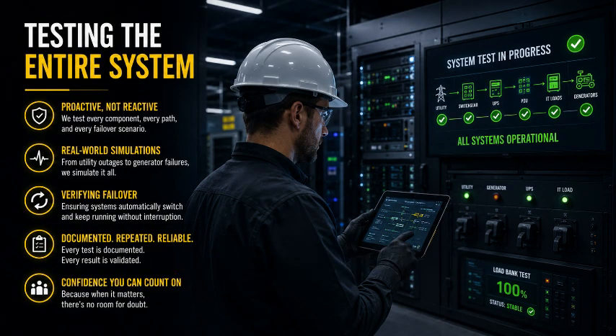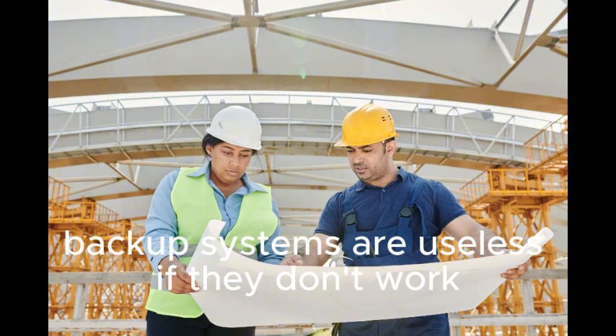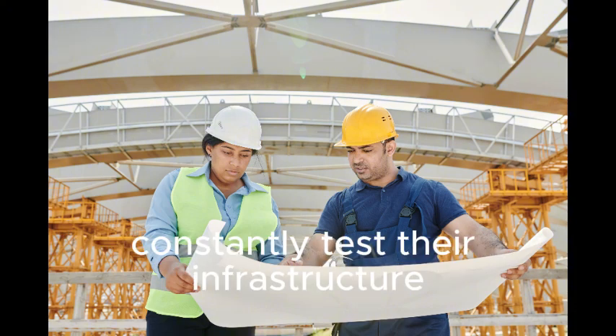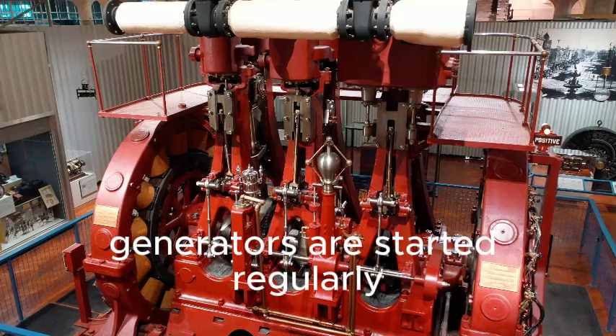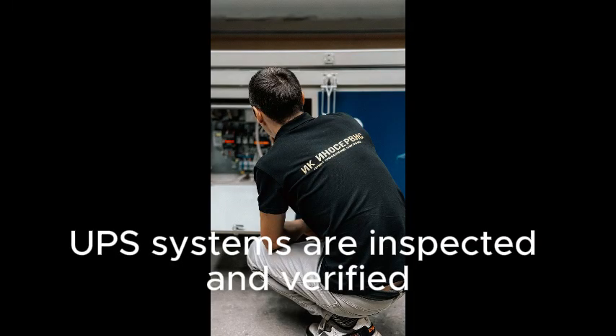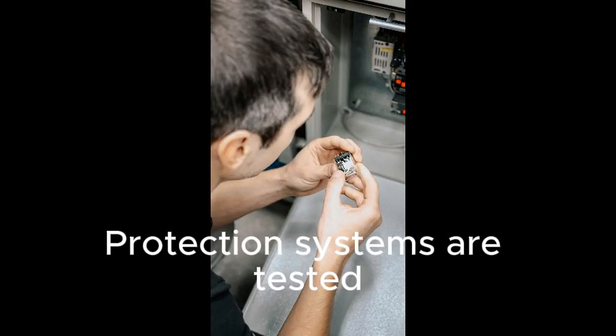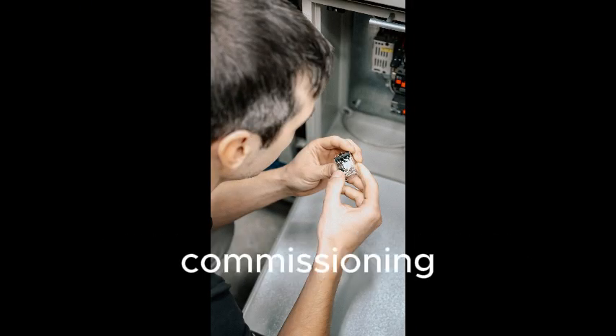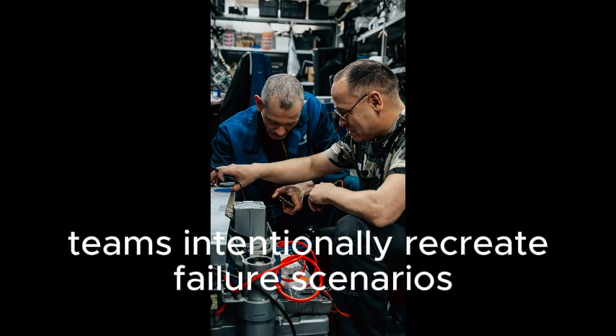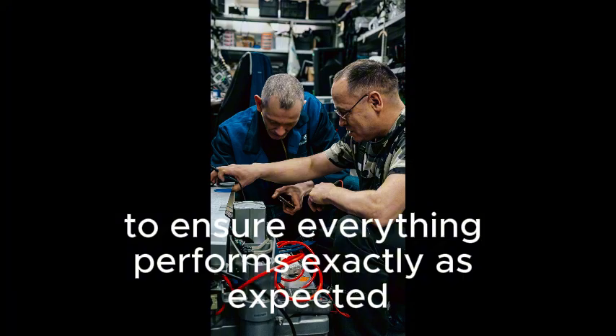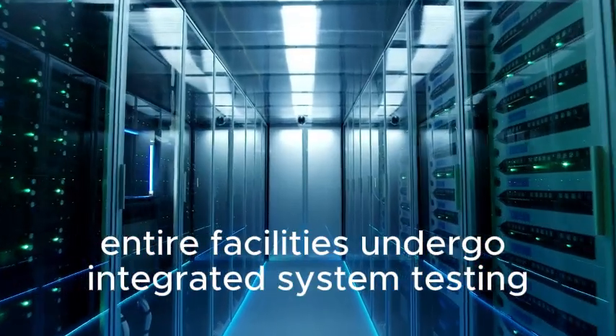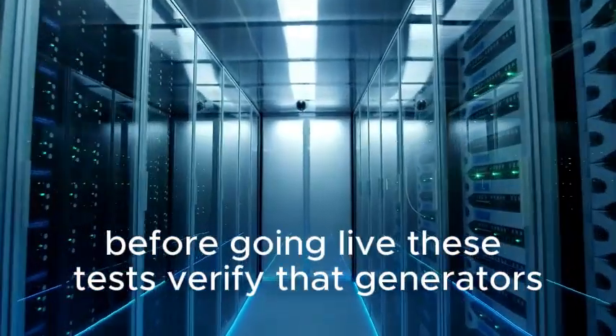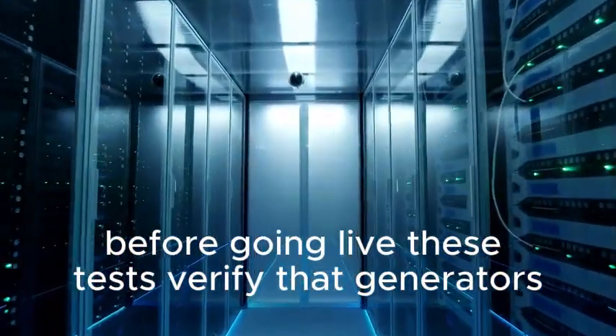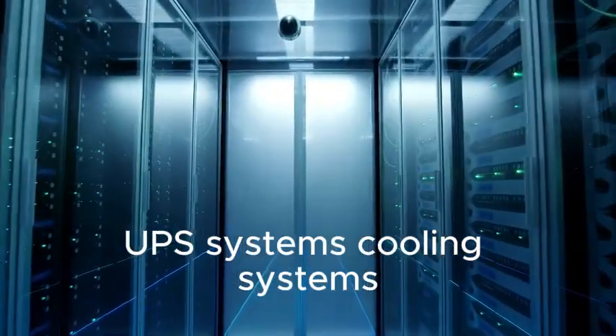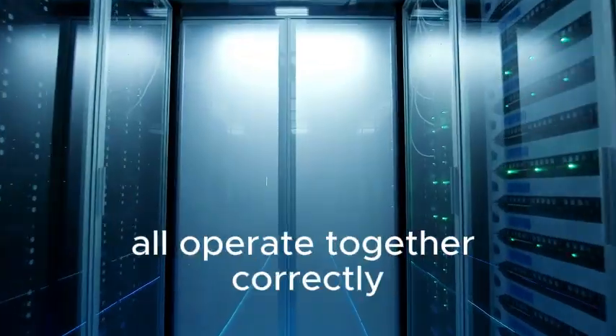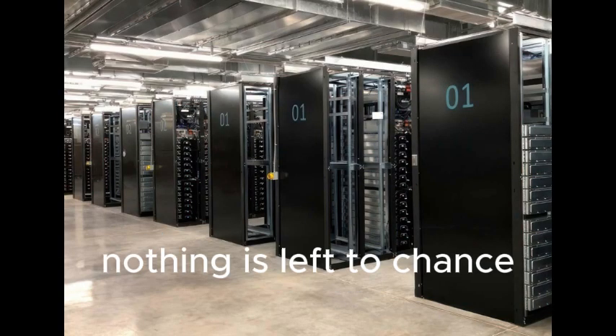Testing everything. Backup systems are useless if they don't work. That's why data centers constantly test their infrastructure. Generators are started regularly. UPS systems are inspected and verified. Protection systems are tested. Transfer sequences are simulated. Commissioning teams intentionally recreate failure scenarios to ensure everything performs exactly as expected. Entire facilities undergo integrated system testing before going live. These tests verify that generators, UPS systems, cooling systems, switchgear, and monitoring platforms all operate together correctly. Nothing is left to chance.